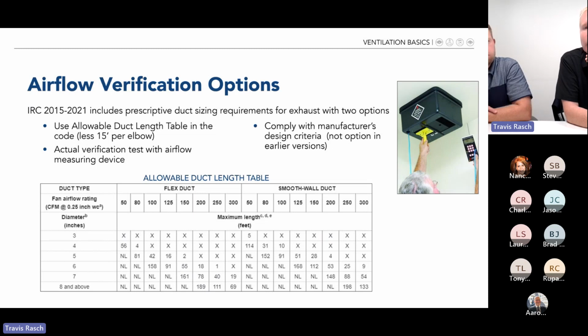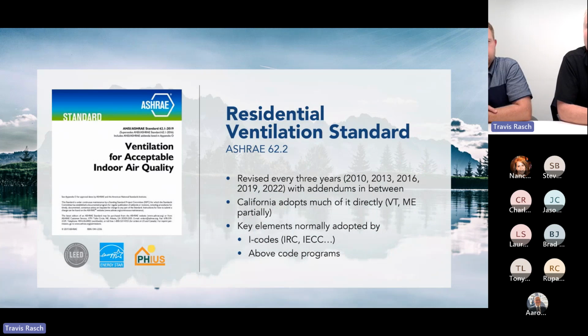But duct length and duct sizes relative to fan performance is really becoming a bigger and bigger issue, as they want to make sure we're getting good ventilation in homes. The second way is to actually do a verification test. You see in the image on the right, this inspector, HERS rater, is actually measuring a bath fan. And the third option is to comply with the manufacturer's design criteria. So the key here, again, the focus in our webinar, is good, healthy indoor air. No matter what type of ventilation system you put in, at the end of the day, you have to make sure it's performing and moving the airflow it's required to.